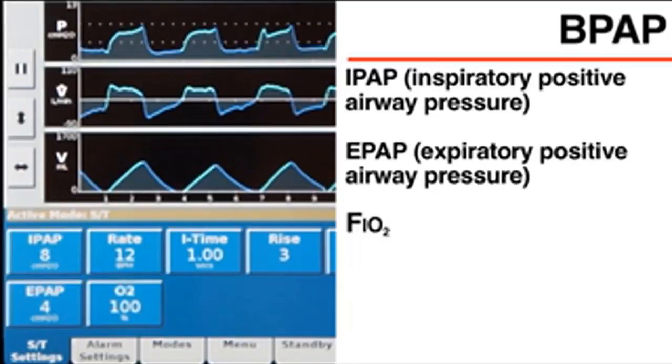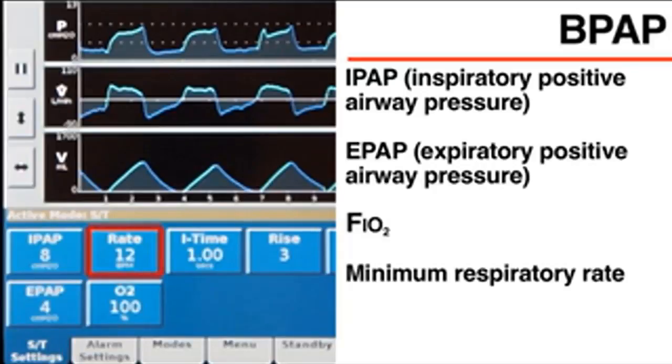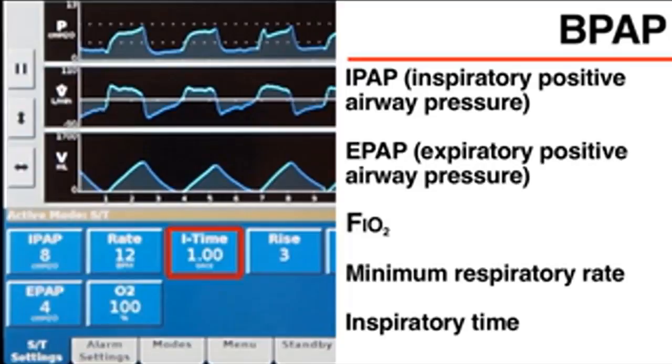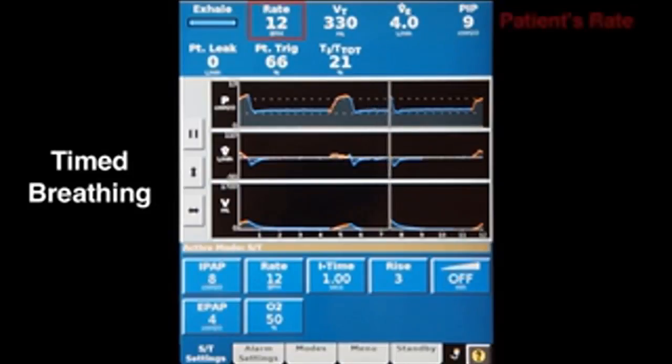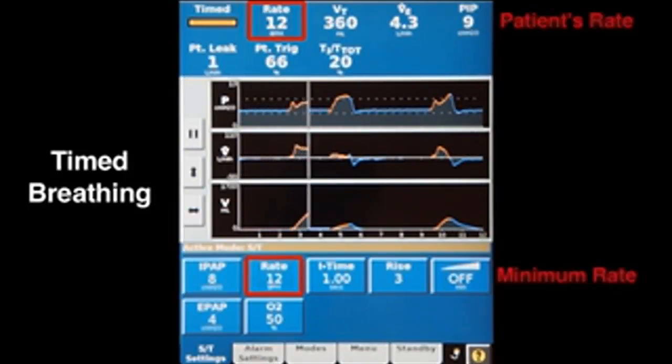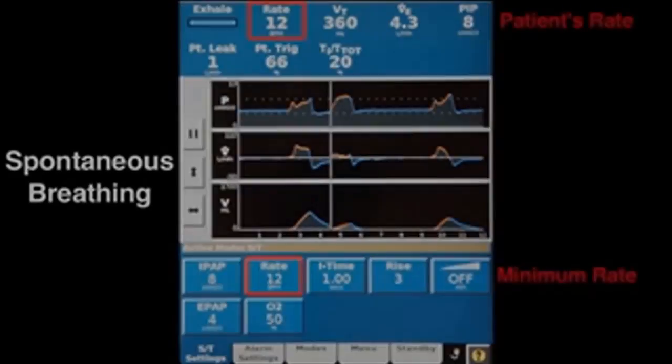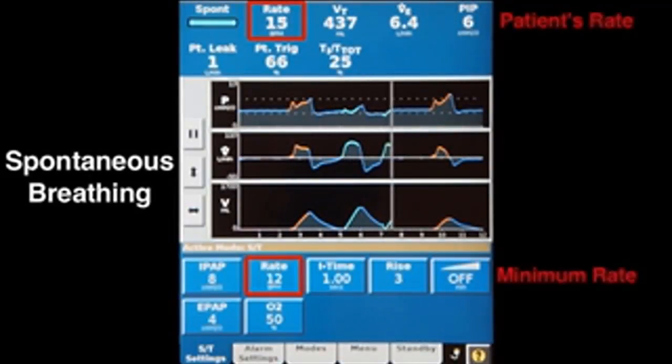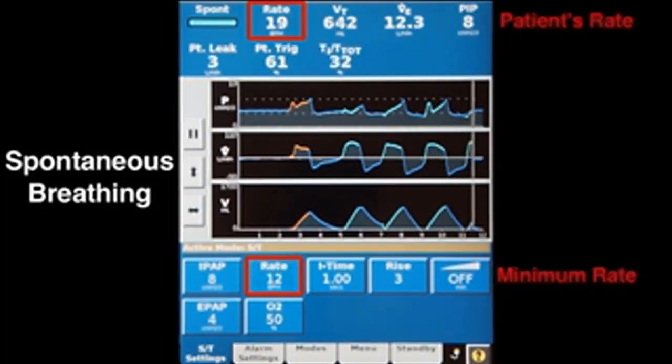BPAP is most often delivered in the combination spontaneous and timed, or ST, mode, in which the settings also include the minimum respiratory rate and the inspiratory time, or I-time. If the patient's respiratory rate is slower than the minimum rate, the ventilator triggers the additional breaths at regular intervals, delivering IPAP for the duration of the I-time. If the patient's respiratory rate is faster than the minimum rate, the patient triggers all breaths, and the ventilator delivers IPAP whenever spontaneous inspiration is detected.